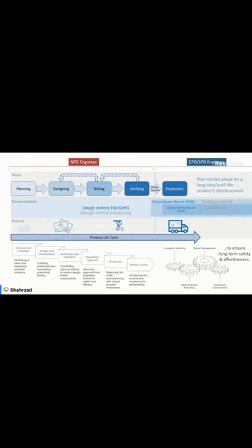market, and the product life cycle that we've seen before. And after it hits the market, the CPD engineers will take care of complaint handling, recall management, adverse event reporting, and continuous improvement and post-market activities. This is to ensure long-term safety and effectiveness for the product, okay? And yes, bear in mind that post-market changes may require regulatory evaluations if they impact safety and performance.